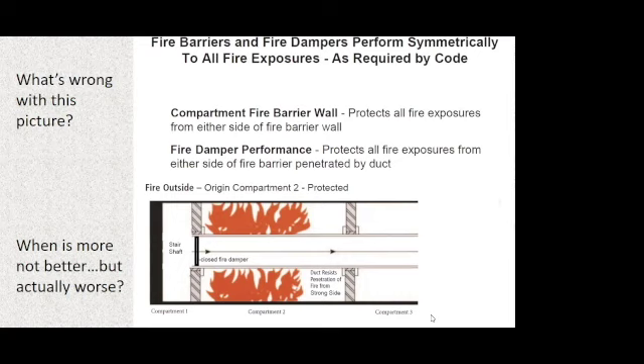So what do we do when we need to get the air moving through the building to get to the stair shaft at one or more levels, to provide a nice even pressure profile that's going to allow the doors to work and yet effectively control the fire products from entering the stairwells? This is one of the most sacrosanct shafts in the building. So getting this right is really important and surprisingly difficult, because what we're looking at right here is the fire scenario that most people think of when they think we need to protect the stair.